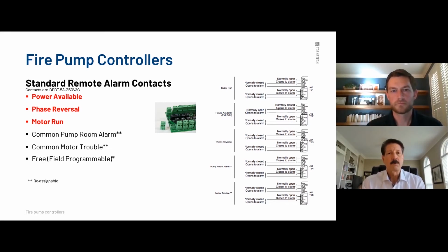The one thing that won't change is the drawings once it's shipped, so you need to make sure you make notes on that. Otherwise, you can pre-order from the factory with an option to have a dedicated remote alarm contact solely for high pump room temperature. But there's a lot of flexibility there. The pull-apart terminals really make life easier for everyone who's connecting to it. I've got pretty good sized hands. I reach in to try to terminate a couple of wires. It's much easier just to pull it apart, terminate your wires, and plug it back in. So it's been streamlined.